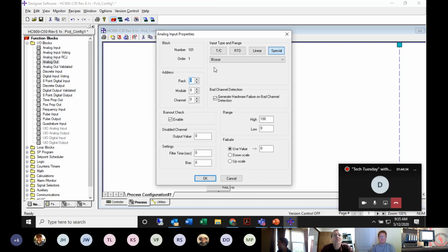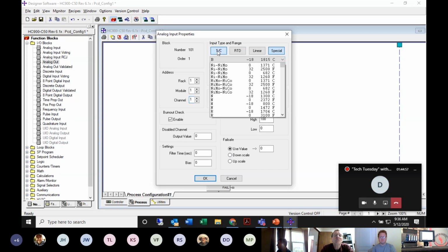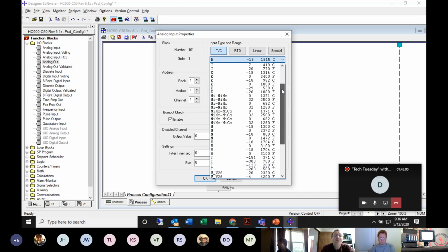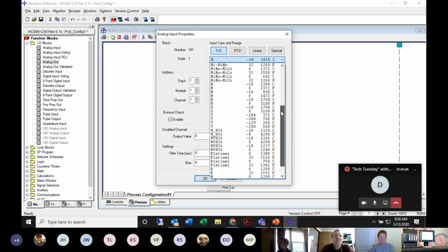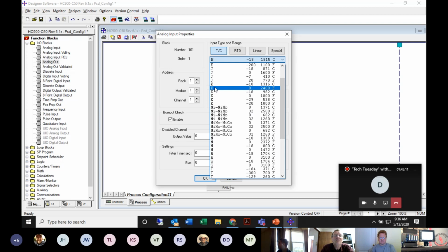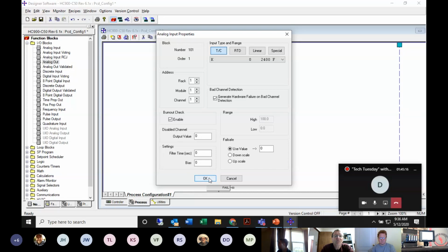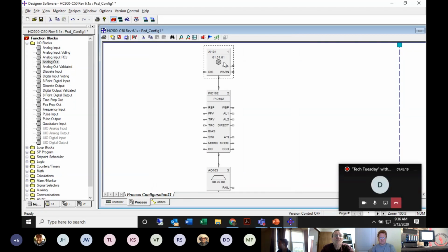On my analog input, if I double click on that block, I can tell it exactly the physical address on my I/O slot. So I'm going to choose rack 1, module 1, channel 1. I can set up filtering if I have a noisy input. I can bias the input. I can set up my high and low range. Also, it's universal. So let's say I have a thermocouple input, and wow, look at all these different thermocouples. Nickel, nickel, moly, haven't used that one in a while. WW26. There's a lot of different ones on here. Let's choose a real typical one, which might be a type K. If I hit OK, now I have a thermocouple input type K, and if I look at the very top of this, it tells me exactly where that's located on the rack: rack 1, module 1, channel 1.